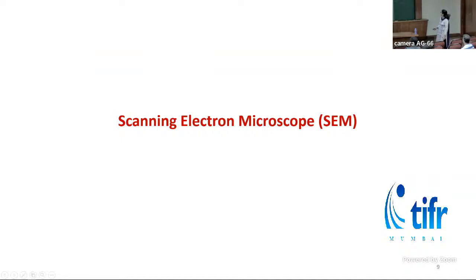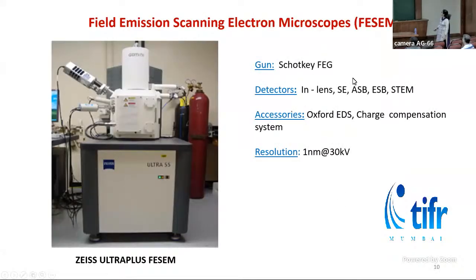Now, going to the scanning electron microscope. This is the FESEM, field emission SEM. It has a field emission gun. So this is a high resolution microscope, and we can resolve 1 nanometer at 30 kV. This machine has Oxford EDX as a detector. And this also has a charge compensation system.